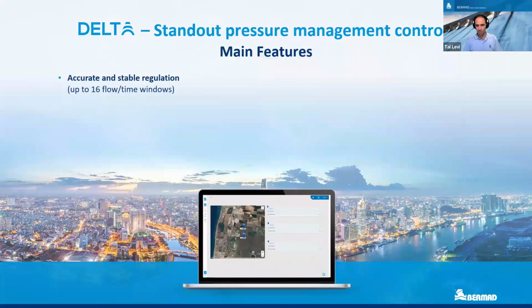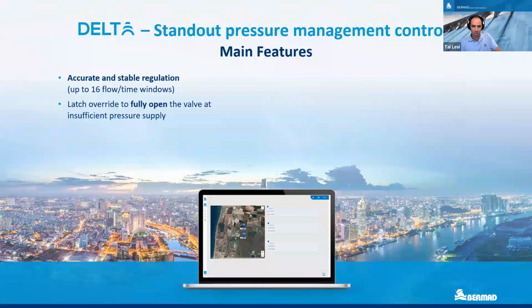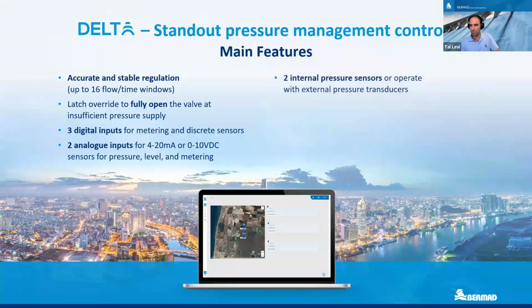Some other main features I mentioned already: we have up to 16 flow or time windows. In places where there is a relatively low pressure supply and you want to fully open the valve in certain hours, we can do it based on a trigger from upstream pressure drop or based on time windows, and fully open the valve, get zero head loss, and that's critical in some places. 3 digital inputs, 2 analog inputs, 2 internal pressure sensors with an accuracy of 0.5%, 0 to 20 bar, and there is also the option to connect external pressure transducers.